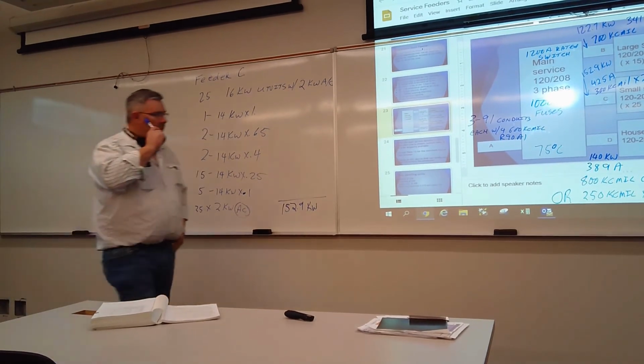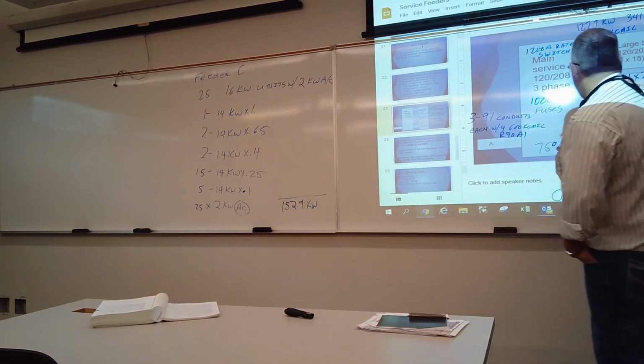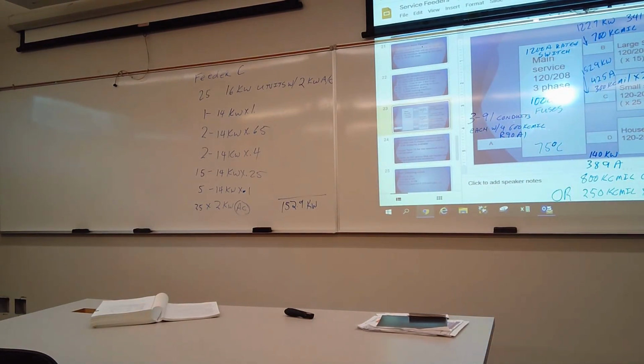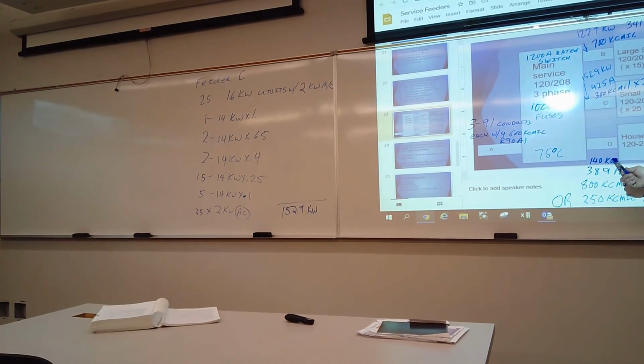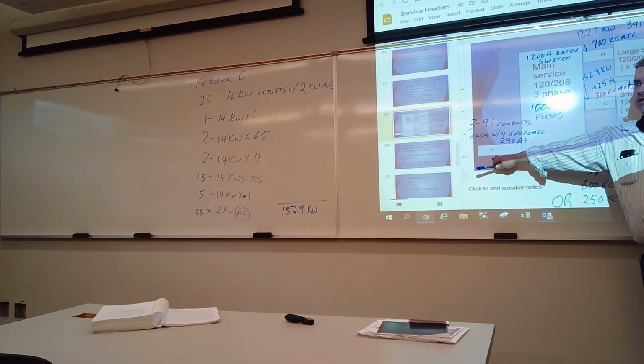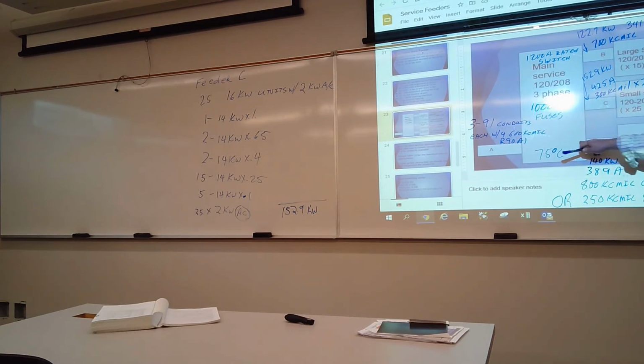A lot of people make the mistake here that when they size that house panel, they size this conduit and everything based on our calculated value times the 75%. And that's not okay, right? This only contributes 105 amps towards this total, but coming from the distribution out to the house panel itself, those conductors have to be able to handle that full calculated demand.